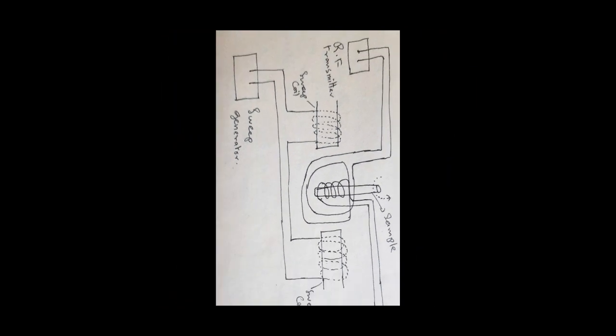Here I want to specify one important point. See, the glass tube, I indicated it with the arrow mark. That means the glass tube is spinning in that direction. What is the reason? You are applying a magnetic field and you are sending the radio frequency waves which are having the precessional frequency in one direction only. So, the molecules which are facing that direction will be promoted to the excited state. The sample will not experience the external magnetic field uniformly. So, to experience the external magnetic field in a uniform manner, the sample tube is in a constant state of rotation. We have a rotator in the instrument.